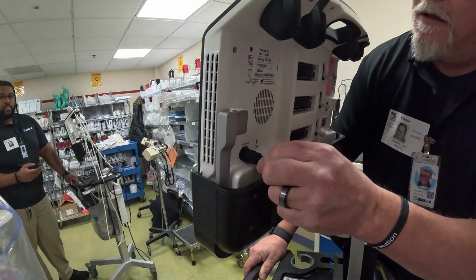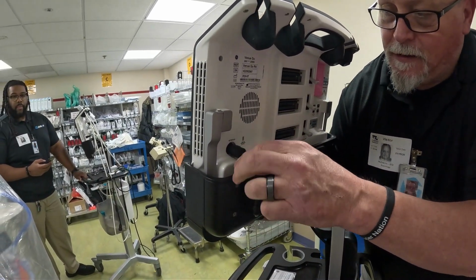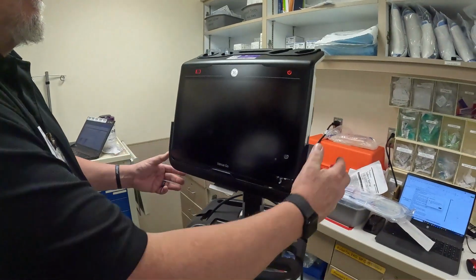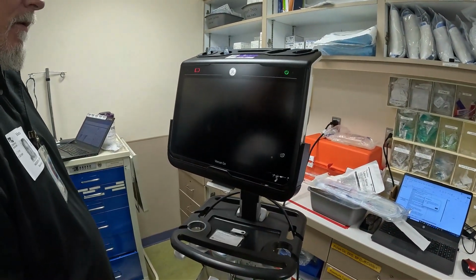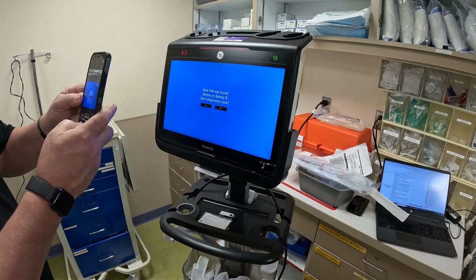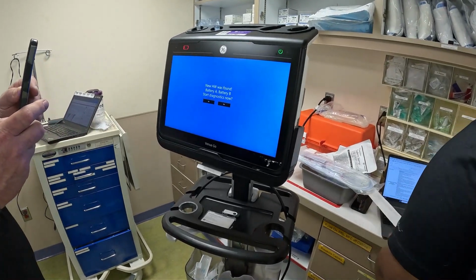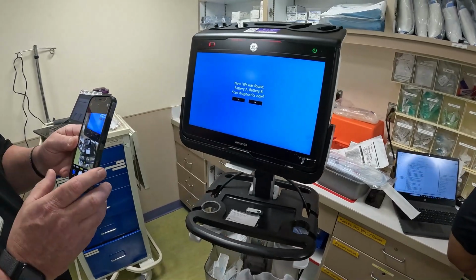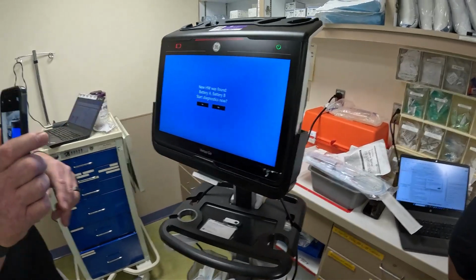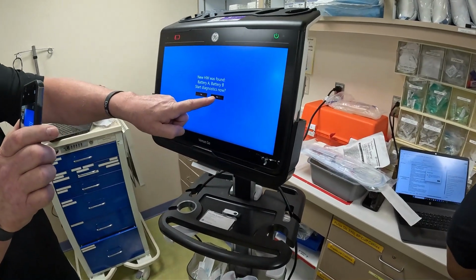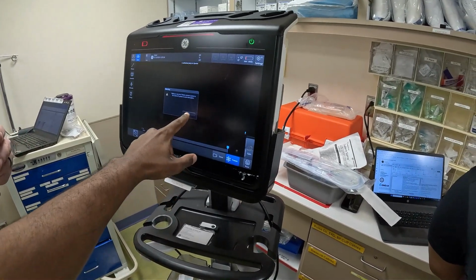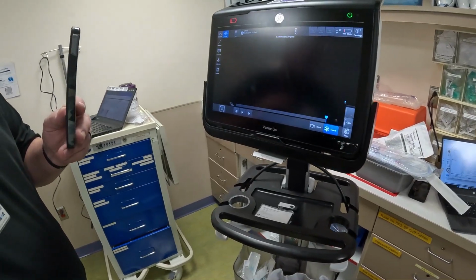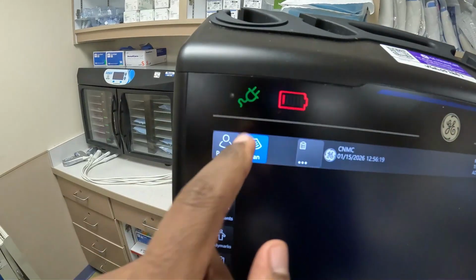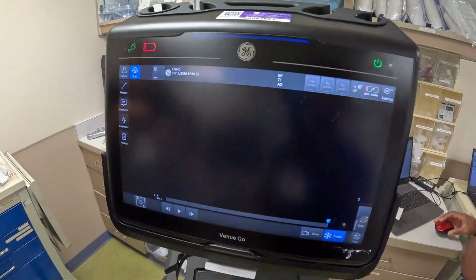You can reconnect the AC power and whatever other cords you disconnected from the device. And you can turn on the device now. Alright, this screen will pop up which says new hardware was found, battery A and battery B. Start diagnostic now. You press no. Battery is very low. You press OK. So when you plug in the AC cord, you have to make sure that there is a green plug on the top left corner. Green plug right next to the battery symbol, which shows that it is charging.